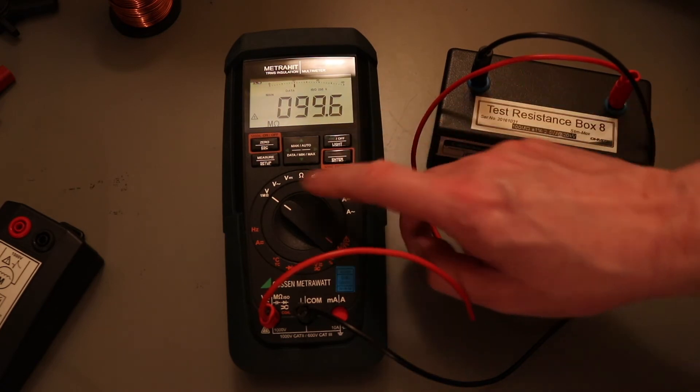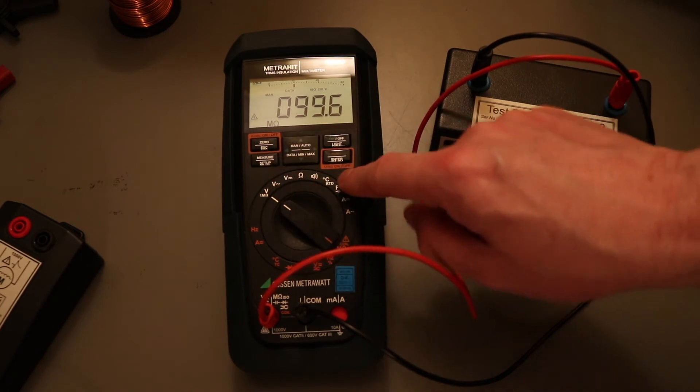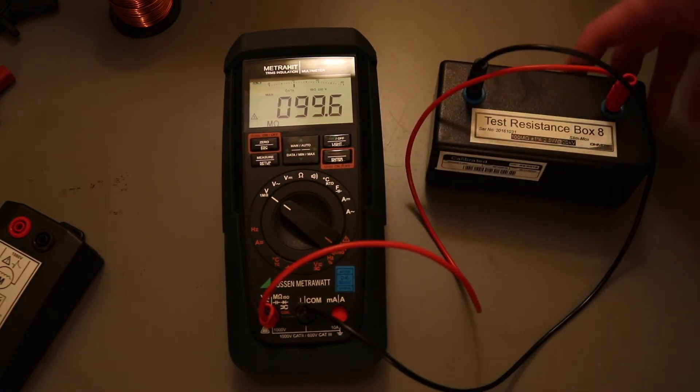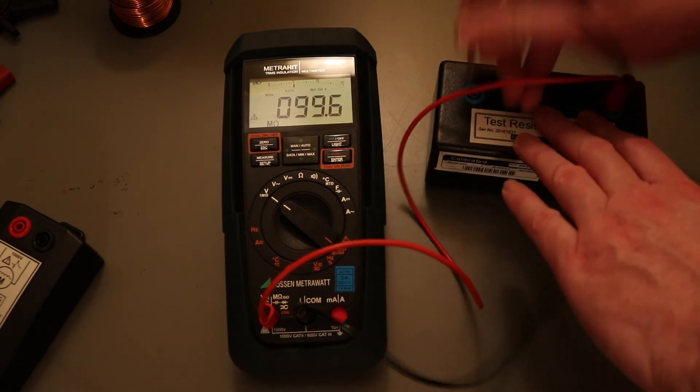You can turn the light on and off but all these other buttons don't do anything now. They're all locked out. The only button that works is the insulation test button. So that's on a test resistor. Say that's a 100 megaohm test resistor. And we've got a 99.6.